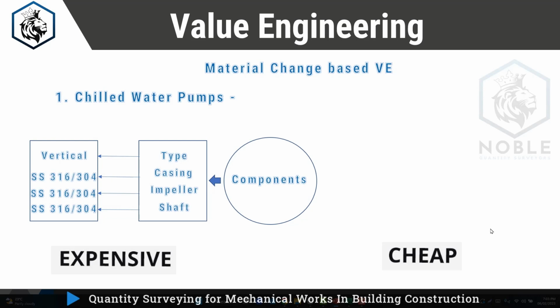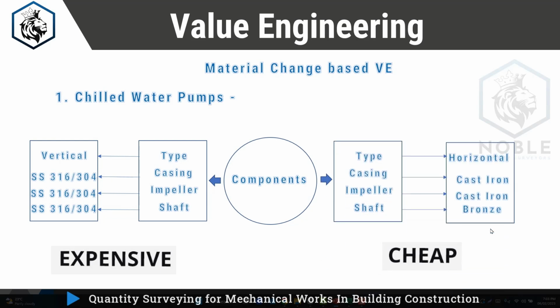So what is the cheaper option? The cheaper option for chilled water pumps is horizontal chilled water pumps. The casing can be replaced from stainless steel 316 or 304 to cast iron, the impellers from SS316 to cast iron, and the shaft from SS316 to bronze material.